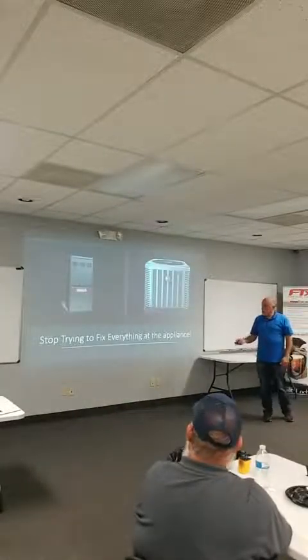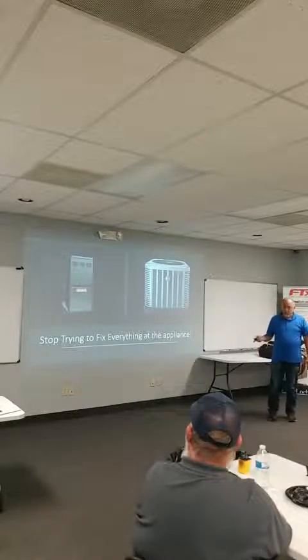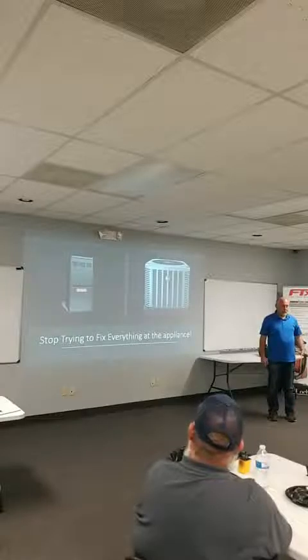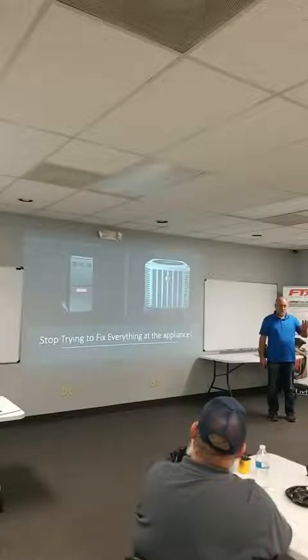So, first of all, in our industry, we got to stop trying to fix everything at the appliance, right? When I say this, I'm serious about this. How many of you guys go out and do a rooftop inspection? You go out there with the jumper wires, you jump the rooftop units, and you never walk downstairs in the building. You never look at the thermostats that control that piece of equipment. You never look at the registers, you never look at the returns, you never pop your head up in the attic and make sure stuff is connected or whatever, right? You're just up there, you service the equipment.